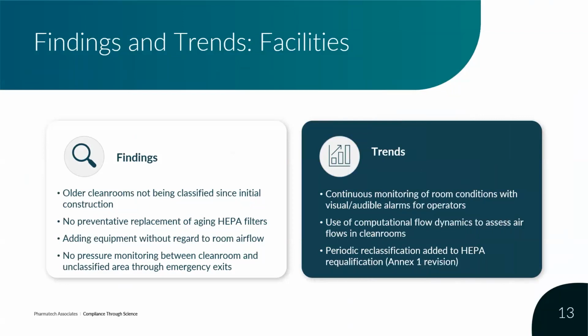First is continuous monitoring of room conditions, such as differential pressure between rooms of different classifications, with a visual and audible alarm for the operators - essentially a horn or a light within the room. This is so that if any issue occurs in regards to the facility operation, operators have immediate notification so they know they can either stop the process or protect the product in some way.